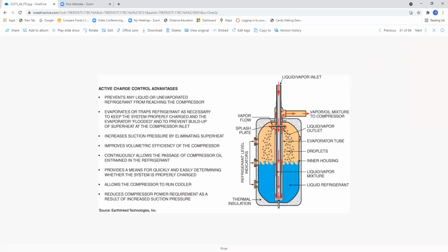to the compressor. We have the liquid vapor outlet, droplets, inner housing. Of course, here's our liquid vapor mixture inside here. This is liquid refrigerant here. And here are those sight glasses. This can actually tell you what the level of the refrigerant is during the various parts of the operation. You'll have a lower level of refrigerant if you have a higher heat load. If you have a low heat load, you will expect to see more refrigerant in this receiver.